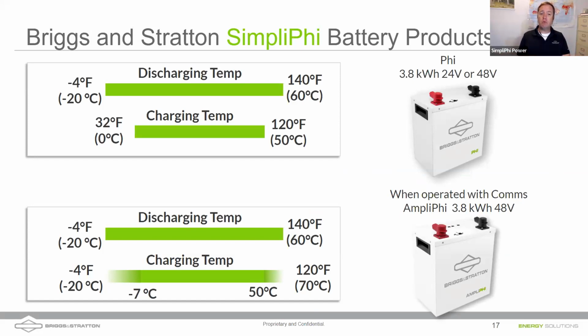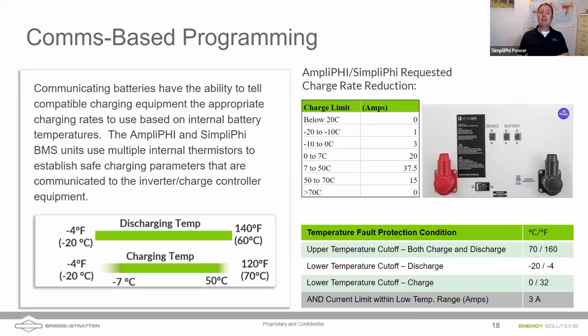But if we're charging, we have to be very careful. With the Phi battery, the non-communicating battery, we want to stay on a more narrow charging temperature range. But using the AmpliPhi battery, which can communicate and tell an inverter the appropriate charging rate based on its temperature, we can charge slowly using the internal resistance, and as Nathan mentioned, jump up to one of those other curves.